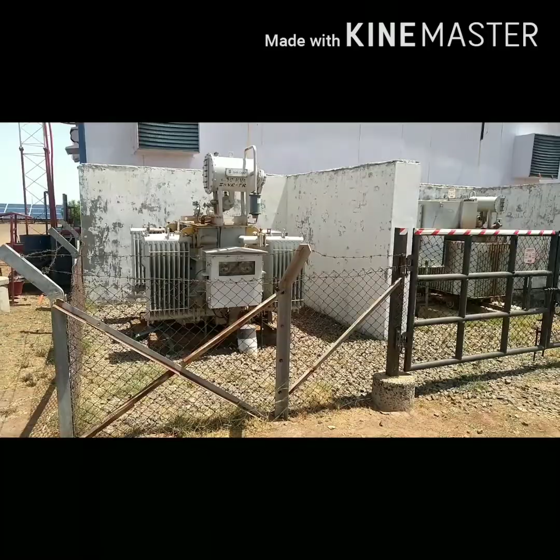From here our switchyard begins. It contains the auxiliary transformer and the main transformer, rated 15 MVA, with two transformers for line 1 and line 2. From here we fetch power up to 66 kV to the Jetco substation. In this switchyard, all gates are locked to restrict unauthorized employees.